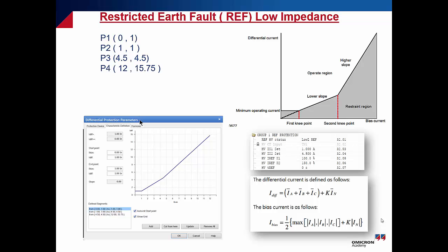But if we have a Siemens relay, for example, or Alstom P633, or a different bias equation, you can use another technique, which is supported by the differential operating characteristic, the same one which we already used for the normal transformer differential protection function. And you will find in the handout helpful files with an application note. It will show you how to use this approach.